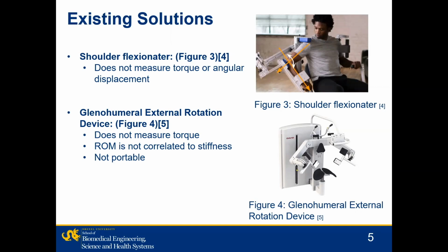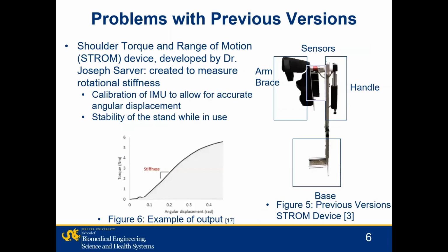So in order to get a portable device to measure stiffness, Dr. Sarver created a prototype device shown in figure 5. The device consists of four parts: a base to support the entire device, an arm brace for users to put their arms on and rotate, a handle part for physicians to assist their rotation, and a sensor part to put an inertial measurement unit, which we call an IMU sensor, to measure angular displacement, and a torque sensor to measure torque. Figure 6 is a sample result of what we expect to get. The x-axis is the angular displacement, the y-axis is the torque, so the stiffness can be calculated as their slope.